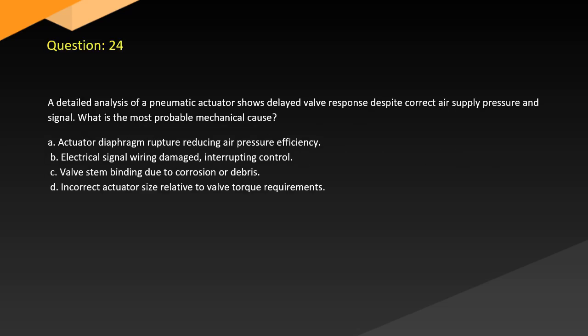Question 24. A detailed analysis of a pneumatic actuator shows delayed valve response despite correct air supply pressure and signal. What is the most probable mechanical cause? A. Actuator diaphragm rupture reducing air pressure efficiency. B. Electrical signal wiring damaged interrupting control. C. Valve stem binding due to corrosion or debris. D. Incorrect actuator size relative to valve torque requirements.